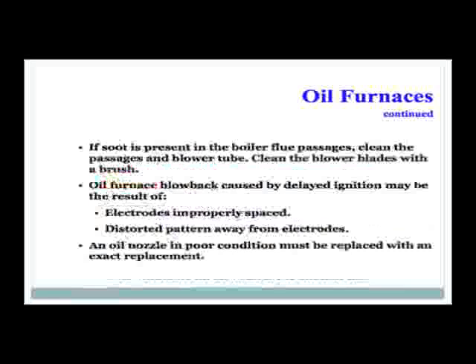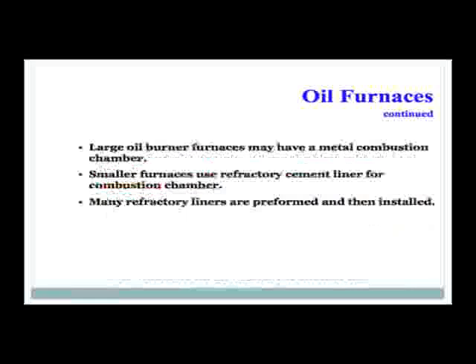If soot is present in the boiler flue passages, clean the passages and blower tubes. Clean the blower blades with a brush. Delayed ignition may be the result of electrodes being improperly spaced or a distorted spray pattern away from the electrodes. An oil nozzle in poor condition must be replaced with an exact replacement — do not vary in size, as it must meet the manufacturer's specifications. Large oil burner furnaces may have metal combustion chambers, while smaller furnaces use a refractory cement liner. Many refractory liners are preformed and then installed.